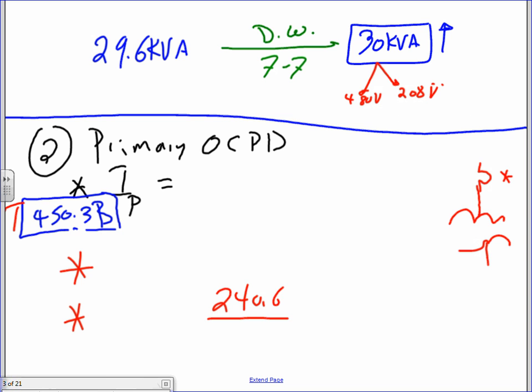How about the 208? 83.3 amps. From this table, guys, from this sheet, it gives you the size of the transformer and the primary current and the secondary current immediately. And if you don't have these two currents, how would you find them, guys? You take the 30 divided by 480 divided by 1.73, you should come up with 36.1. Take the 30 divided by 208 times 1.73, you should come up with 83.3. But the table will give it to you right from the get-go to make it easier.